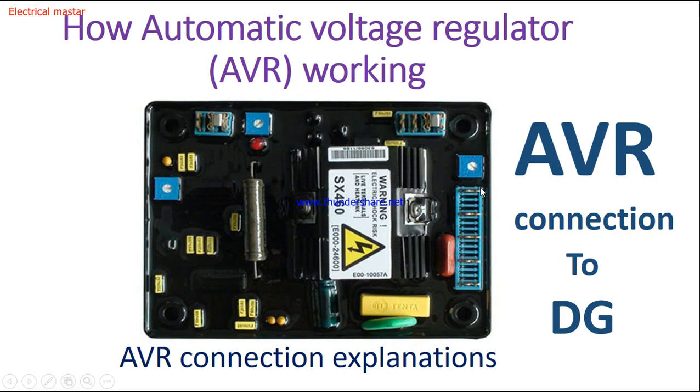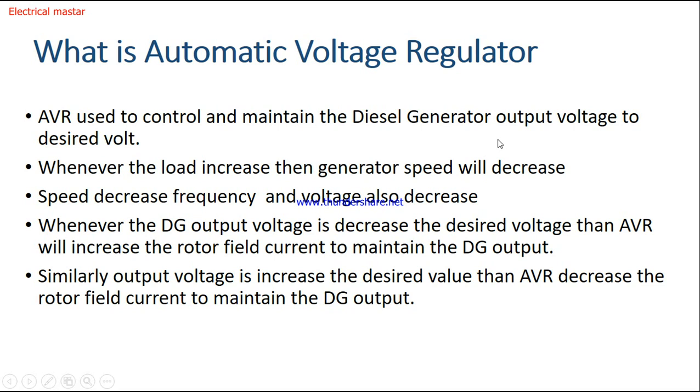This is the AVR — automatic voltage regulator — model number SX460, for three-phase generators. AVR is used to control and maintain the diesel generator output voltage to the desired level. Whenever the load increases, the generator speed decreases, and frequency and voltage also decrease. We want to maintain the output voltage constant for all operations — whether full load or no load — and for that purpose we use an automatic voltage regulator.